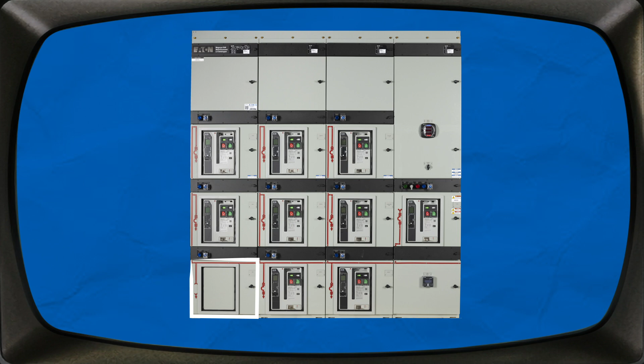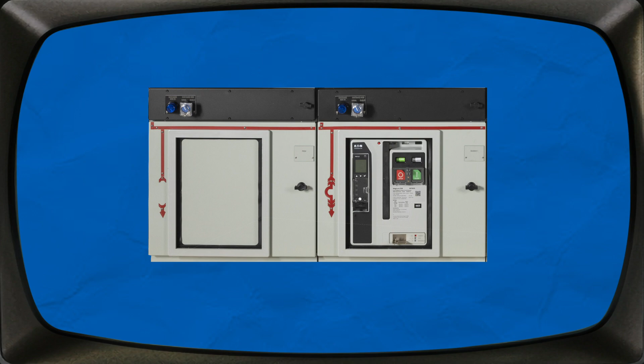First up is the provisional compartment. This is a compartment that has been configured to be used as a breaker cell at some point in the future. The compartment is specified like a standard breaker compartment and is built in a similar fashion. The main difference is the compartment does not come with a breaker installed and has a cover in its place.